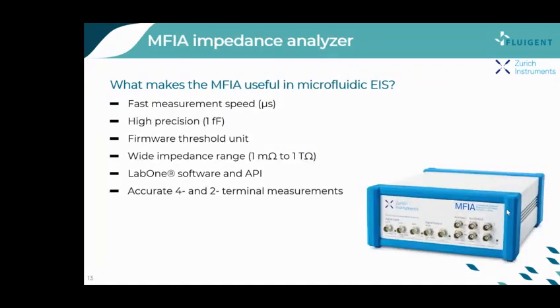Another of our instruments, the MFIA impedance analyzer, is also a great fit for microfluidic applications. The MFIA can measure the impedance very fast, allowing the passing analyte to be measured on the microsecond time scale. In addition to its high impedance accuracy, the MFIA can also measure over a very wide impedance range, from 1 milliohm all the way up to 1 teraohm. It is very precise, so you can resolve even very tiny changes in the dielectric signal. It also includes a firmware threshold unit, which can be used to trigger an output sourcing voltage based on the measured signal.